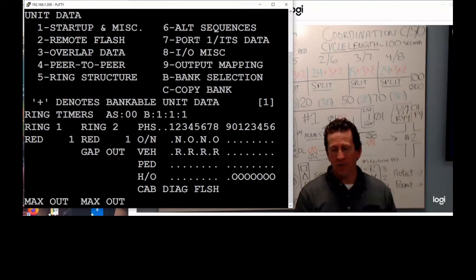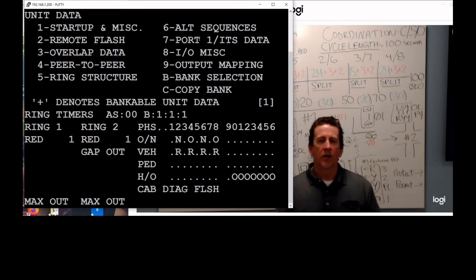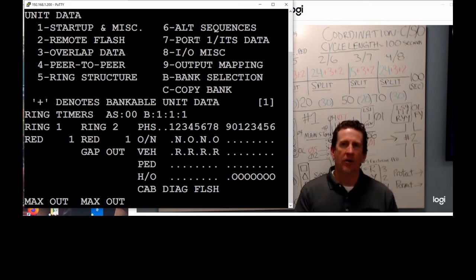Same thing with the SDLC cables. Some cables are pinned out all the way. The ones that have a full complement of pins in the connector are the ones that tend to work better. Siemens does a really good job where if you look in a cabinet, you'll see where the 5 harnesses connect to a hub assembly, and some manufacturers take the other end and put it on a termination block.